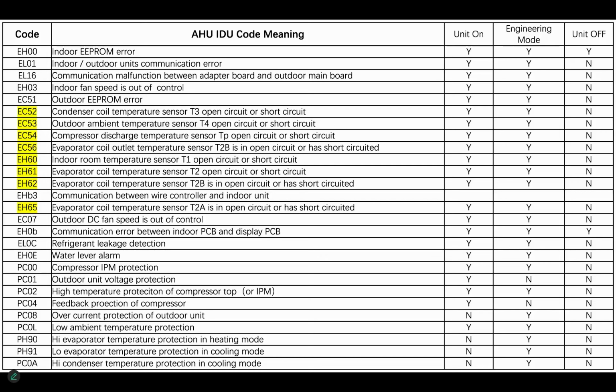The other one I want to look at is the PC00. That can also be a PC04. I know PC04. Yeah. So PC00 can be part of about 10 different faults. What PC00 is, it's a problem with either the compressor or the inverter. So you have one of those faults that's in the PC40 range, anywhere PC40 to PC49, or a PC00.